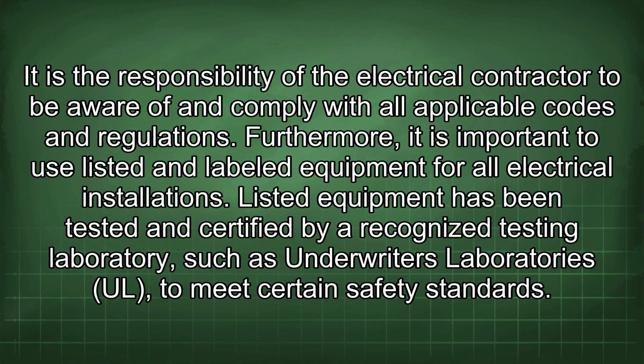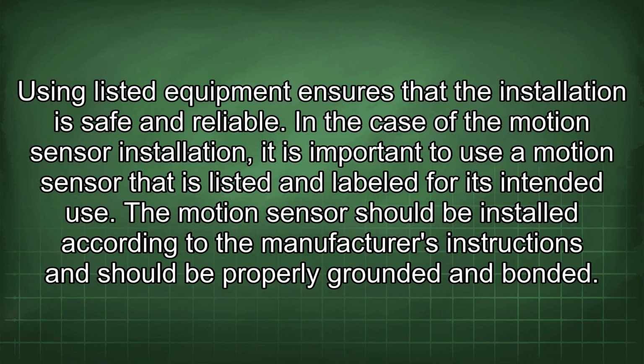Furthermore, it is important to use listed and labeled equipment for all electrical installations. Listed equipment has been tested and certified by a recognized testing laboratory such as Underwriters Laboratories (UL) to meet certain safety standards. Using listed equipment ensures that the installation is safe and reliable. In the case of the motion sensor installation, it is important to use a motion sensor that is listed and labeled for its intended use.